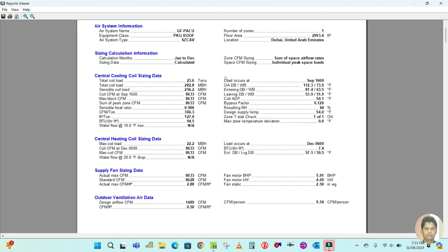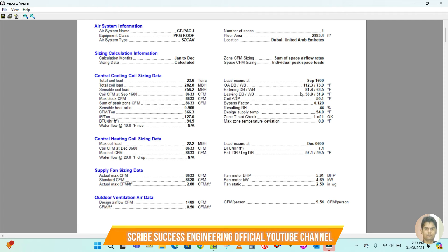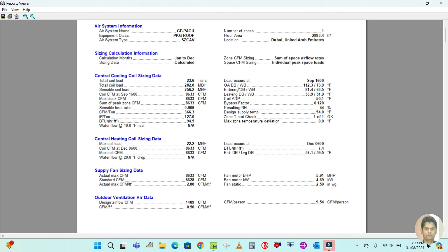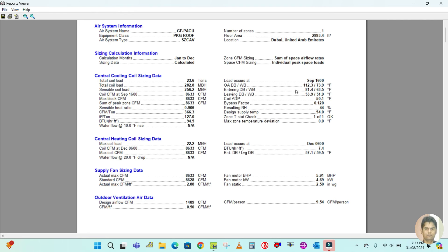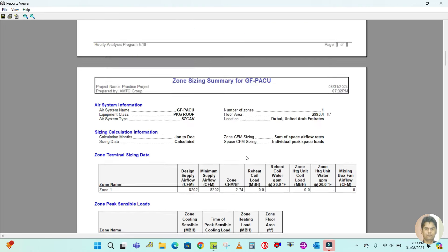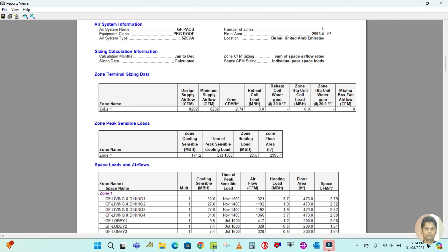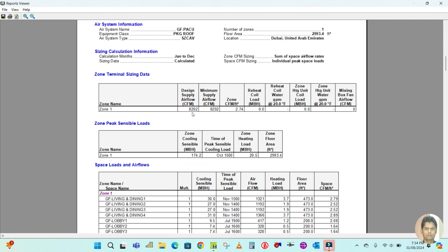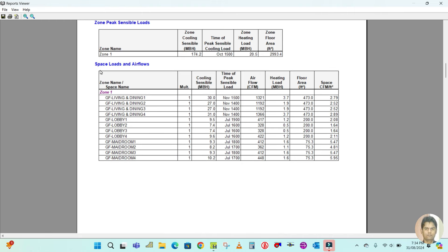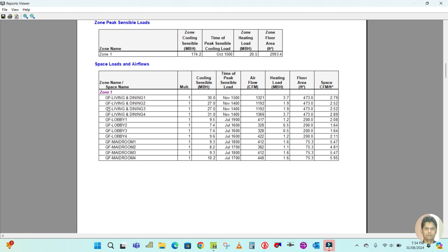Here is the floor area, location, and the number of zones is one. The central cooling sizing data shows the total coil load is 23.6 tons. The supply fan sizing data shows the actual maximum CFM is 8,633 CFM, and this is the fresh air requirement. On the right side, the peak load occurrence month and time are given, along with outdoor air dry bulb value — the on-coil and off-coil, coil ADP, and bypass factor.